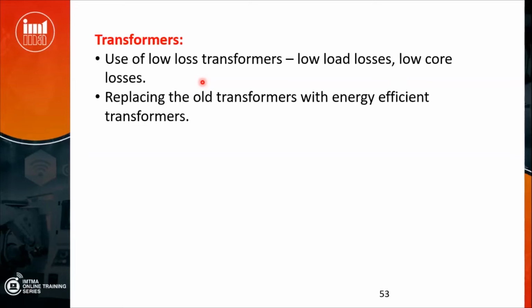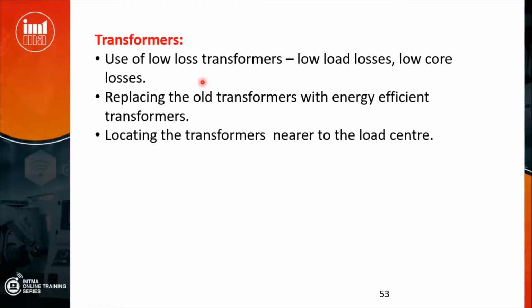If you have a voltage problem, before that, locating the transformer nearer to the load center is very important, because as the wire or cable length increases, resistance increases, voltage drop increases, and voltage regulation is affected. So the ideal is to keep the transformer at the center of the load. But in many places it is not possible. I know you can't place the transformer in the center of the hangar. However, you must bear in mind how far you can make use of this concept.